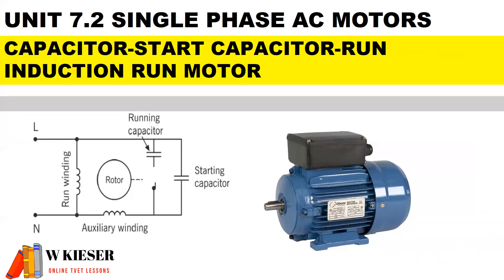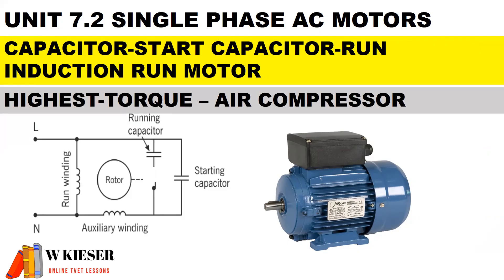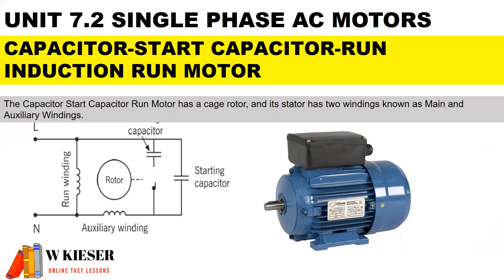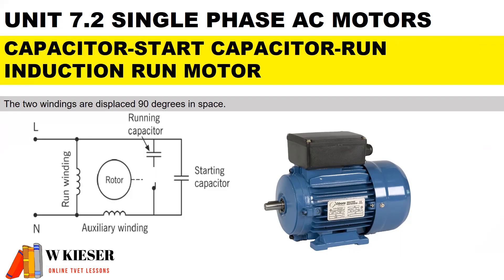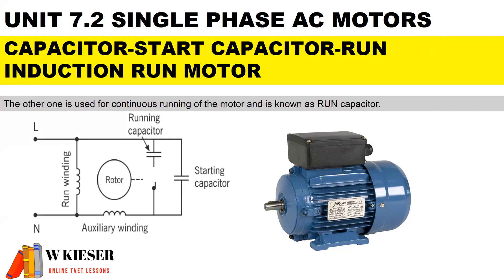Here we have the capacitor start capacitor run induction motor, and it's important to note that there are two capacitors. It has the highest torque, and a good application is air compressors or refrigeration. This motor has a cage rotor, and its stator has two windings, known as the main and auxiliary windings. The two windings are displaced 90 degrees in space. One capacitor is used at the time of starting and is known as the start capacitor. The other one is used for continuous running of the motor and is known as the run capacitor.